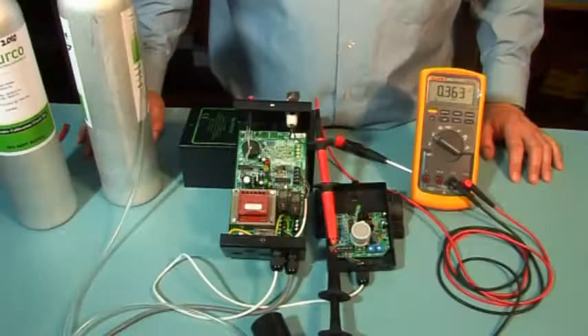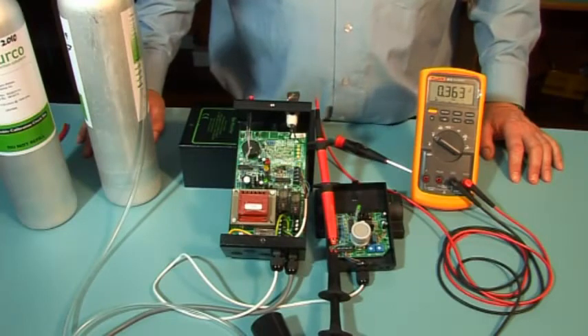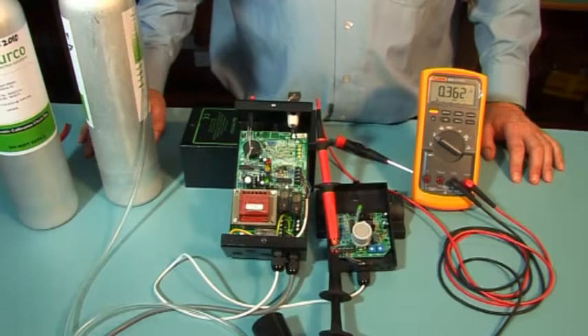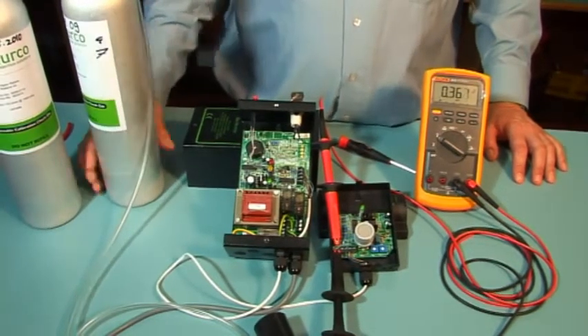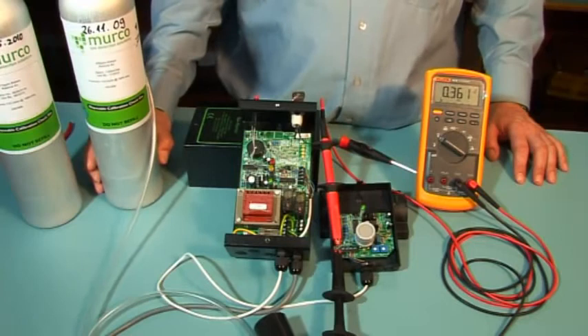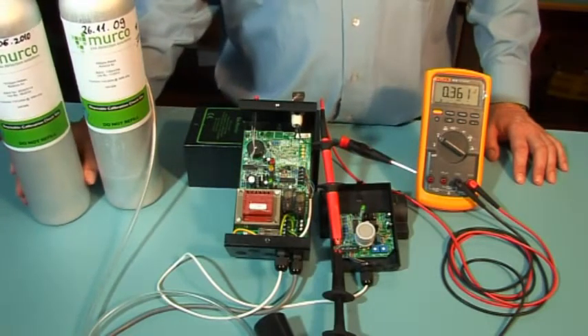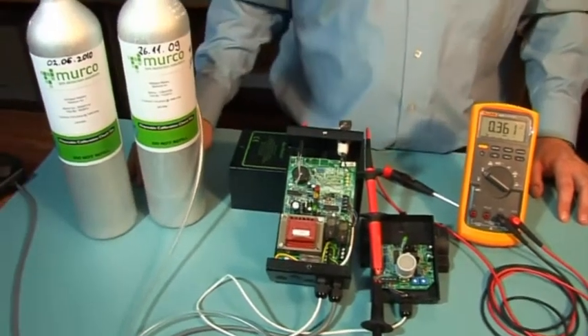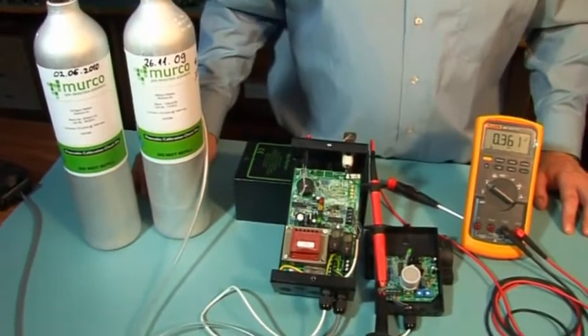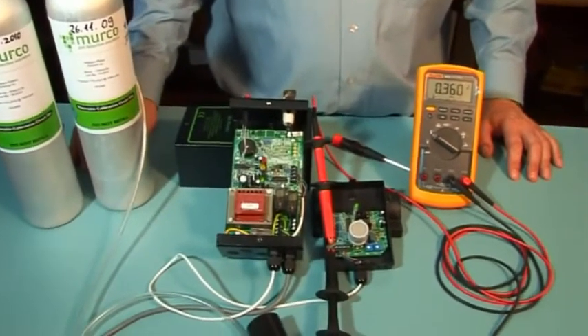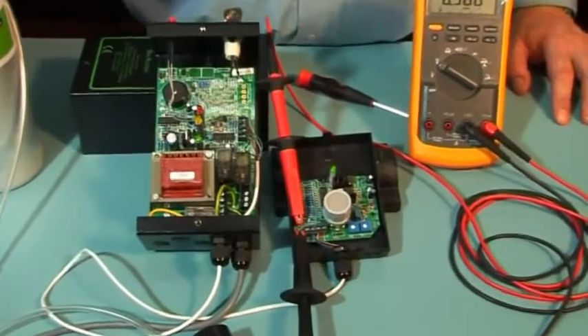There are 2 ways to carry out this calibration. One is to calibrate for the high-level alarm and use the electrical values to set the low level. This requires 1 cylinder of gas, and the other is to use 2 cylinders of target gas, 1 for each of the low level and high level. For the purpose of this test, we will use 2 cylinders of target gas.